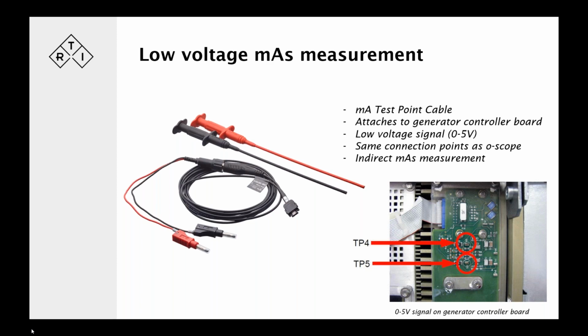If you're measuring it with a scope, of course, then you need to look at the ramp up and the ramp down and the signal itself, and do your own calculations many times. Here, the software takes care of these calculations along the way. So it's quite a convenient way of getting the mA and the mAs signals, if you don't have a high tension cable available, and if it's tricky to reach the jumper points in the generator for the MAS1 connection. And of course, here we're on the low voltage side of it, so it's not as scary as if you go into the generator itself and open that up. So that's the mA test point cable.